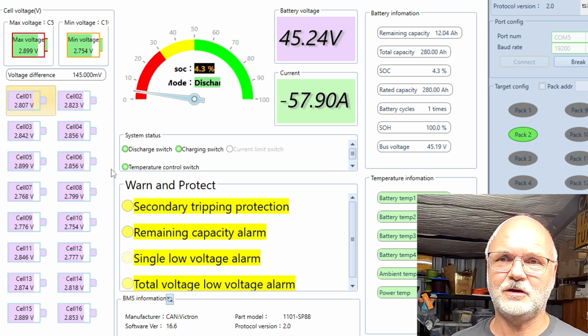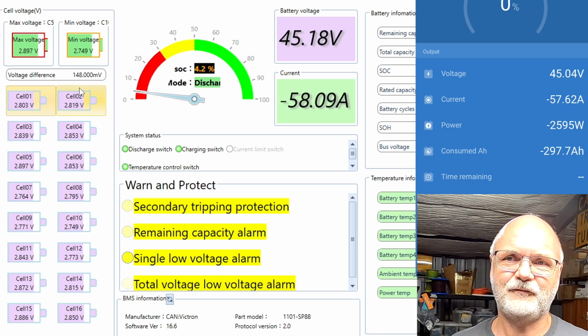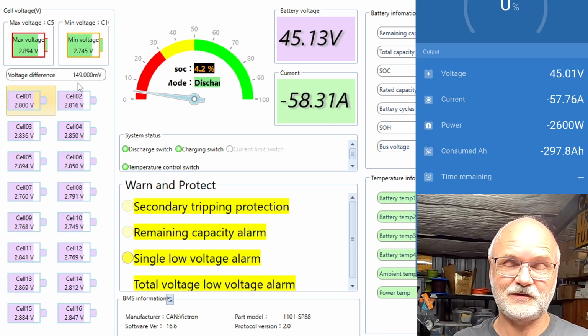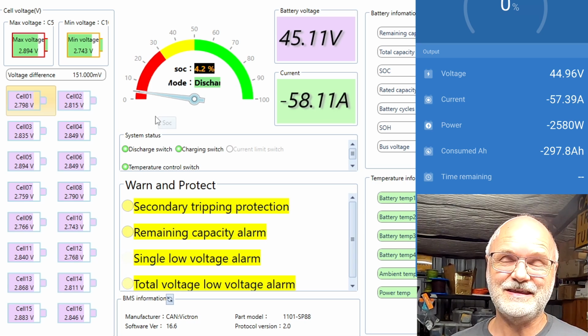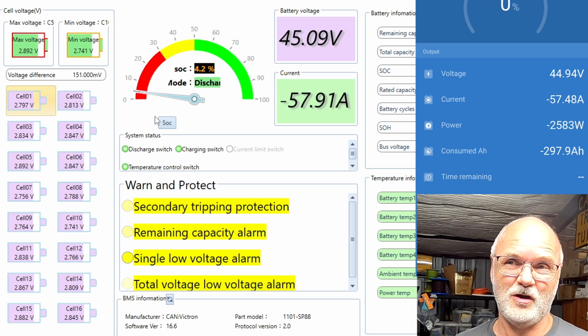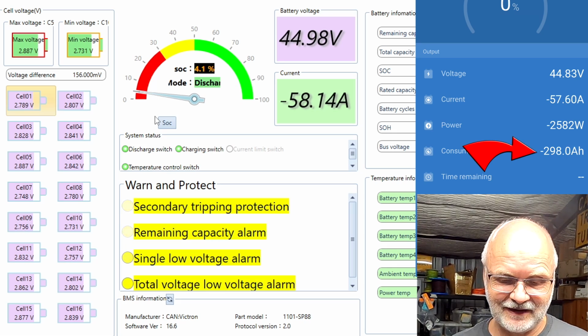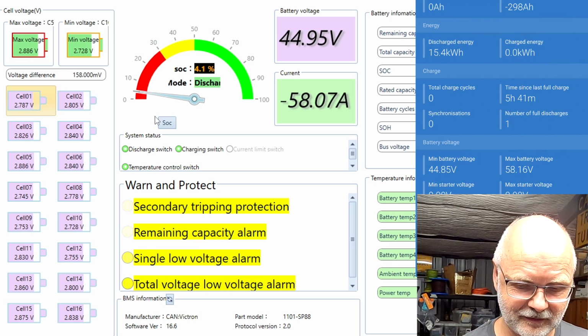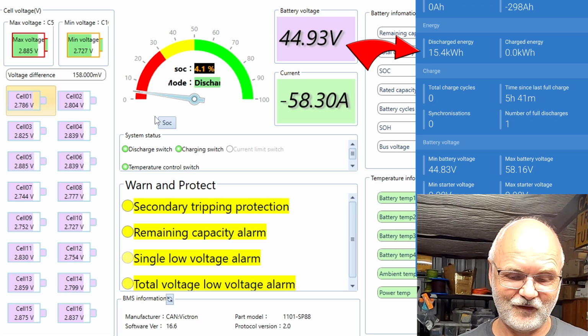All the cells are under 2.9 volts now, 150 millivolt deviation. This will obviously go up now, and we may see a disconnect of the inverter before we actually hit 2.5 volts. So 298 ampere hours, 15.4 kilowatt hours so far.